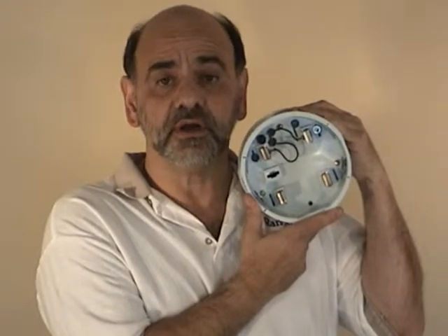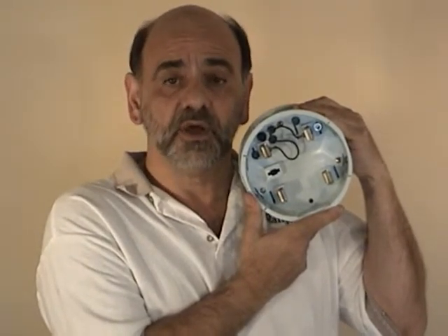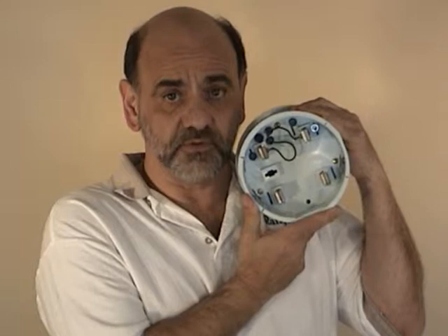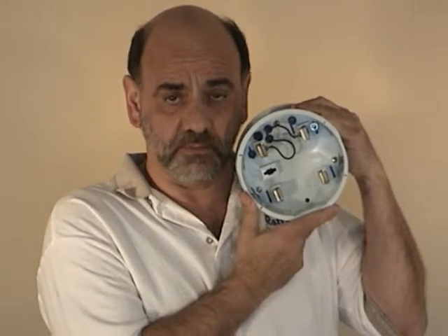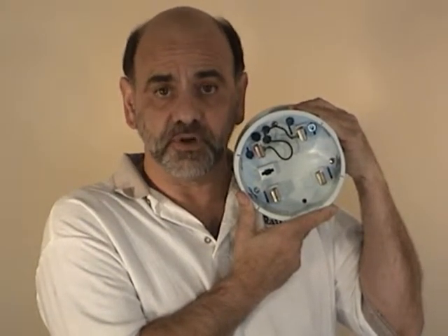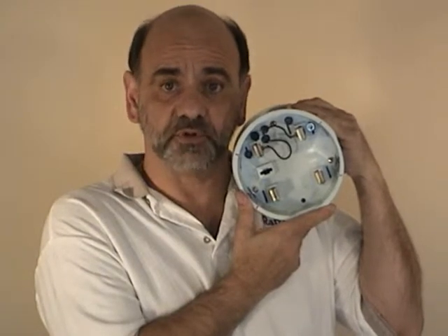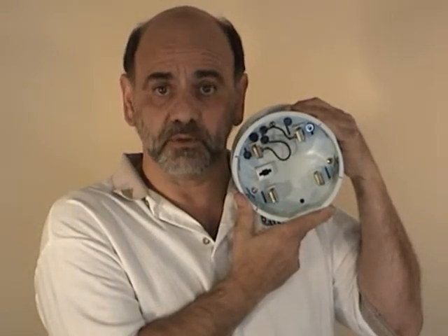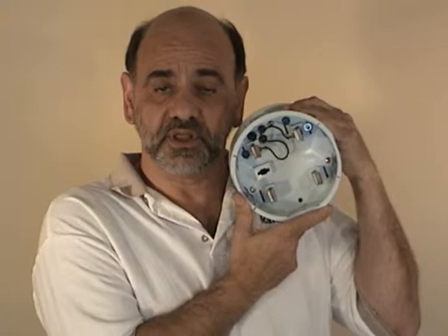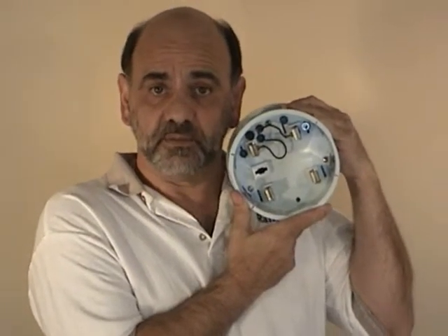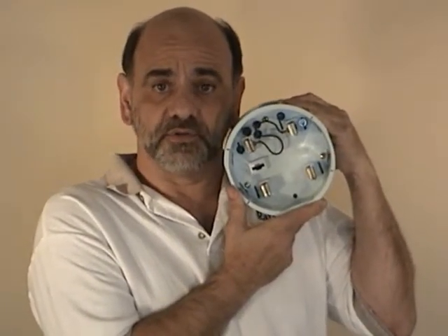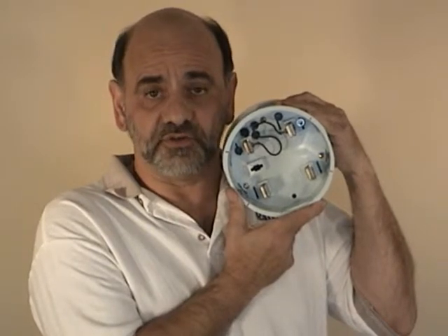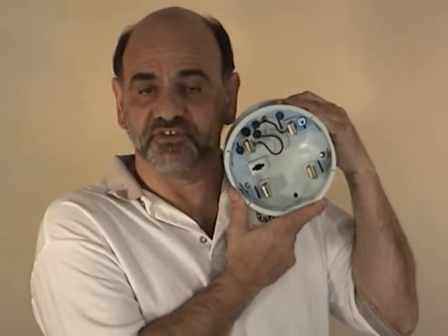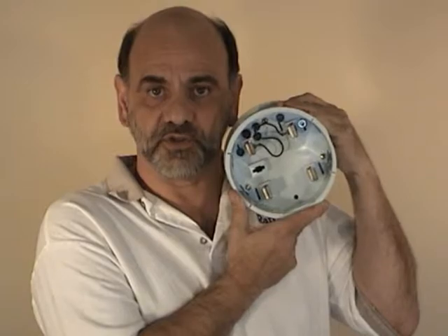Remember, our unit here with the 1 megabyte of memory will download up to 230.4 kilobaud, depending on if your computer can achieve those levels. With 1 megabyte of memory, you want to be able to download these things fast. Typically 115 kilobaud or 230 kilobaud is what you really should use on the 1 megabyte. Then you get through this in just a few minutes. Thank you very much. We'll go to the computer now.